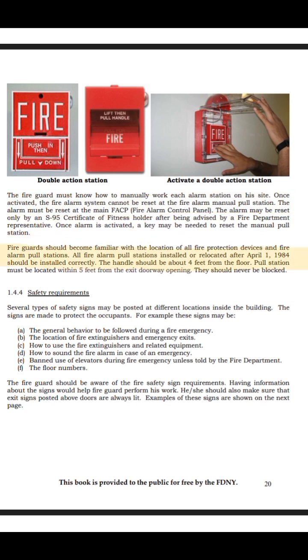Fire guards should become familiar with the location of all fire protection devices and fire alarm pull stations. All fire alarm pull stations installed or relocated after April 1, 1984 should be installed correctly. The handle should be about 4 feet from the floor. The pull station must be located within 5 feet from the exit doorway opening. They should never be blocked.